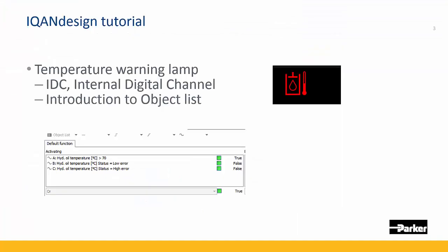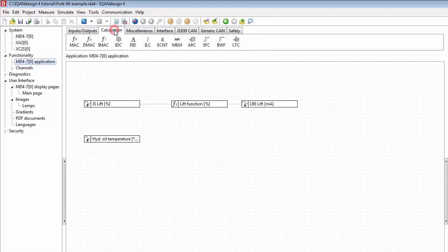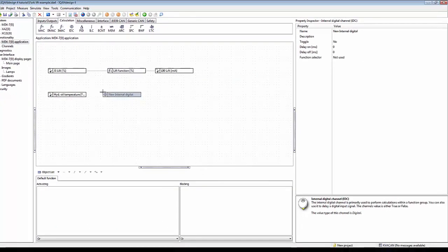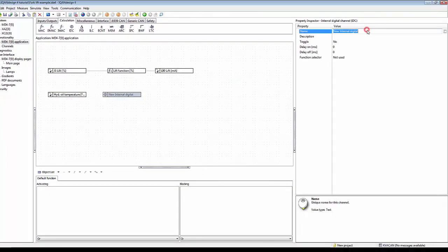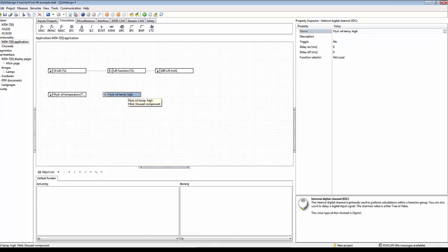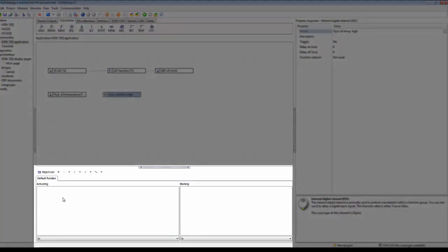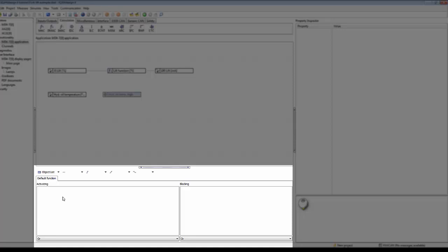To control the lamp, we need a new channel. Let's go back to the MD4 application here. Under calculation, we find IDC internal digital channel. Let's name this hydraulic oil temp high, so this will be true when the hydraulic oil temperature is above our limits. Here I have it selected to be using the method object list.